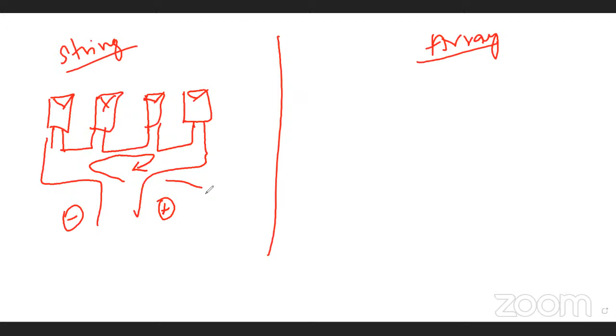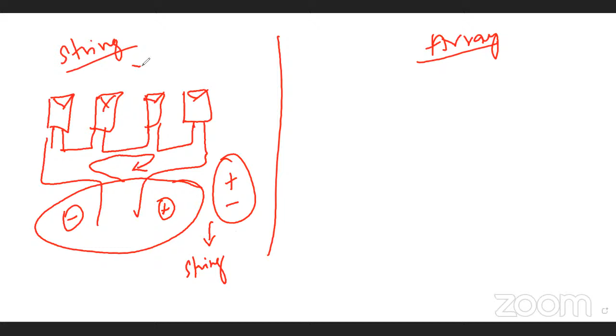There are two things: one is the string, another is the array. The main difference between string and array is this: this is the electrical symbol of a PV module. Let's say you have 4 modules. When the 4 modules are connected in series, this connection is called a series connection, creating a loop of PV modules. This loop gives an output of 1 positive and 1 negative terminal, and this is called a string. So in simple words, a string is nothing but the electrical arrangement.